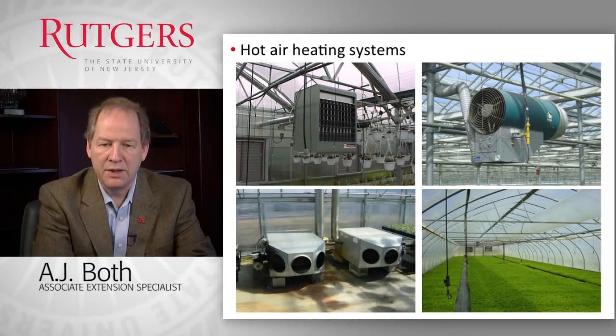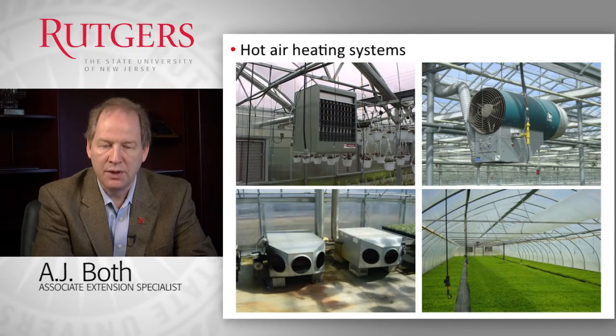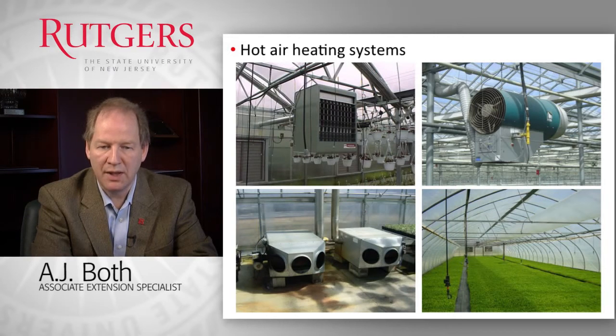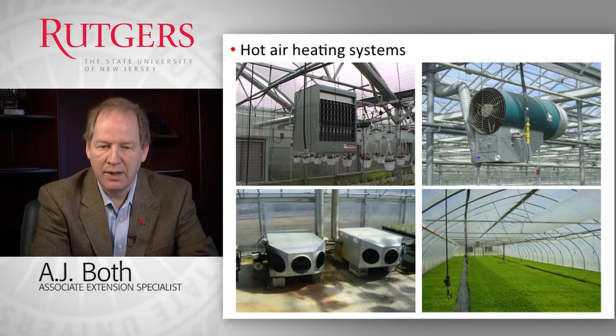More common are hot air heating systems. We have unit heaters that are typically installed alongside walls that blow jets of warm air into the greenhouse. An issue of how we provide combustion air and how we expel that combustion air is of concern. Sometimes we see systems that have separated pathways for the incoming combustion air as well as the exhaust air, to try to prevent any potential problems with gases that may contaminate the greenhouse environment.